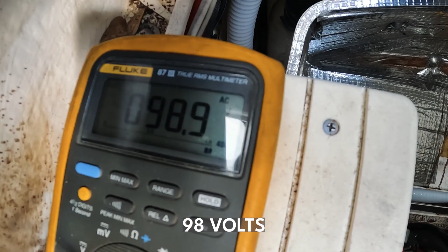Next step in the problem solving: we hooked up a multimeter directly to the generator to make sure it's actually putting out electricity. This is right off of the actual generator, but it has no load on it, so it's not going to put out the full 110, 115 unless there's an appliance or something actually pulling that voltage.